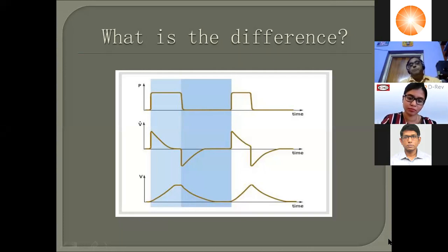So this is a supported breath. In a supported breath, your flow never touches your baseline. Where it ends depends on the flow termination criteria. In many ventilators, you can actually set the flow termination criteria as you wish, and in some ventilators, you cannot set it. It is set by default.